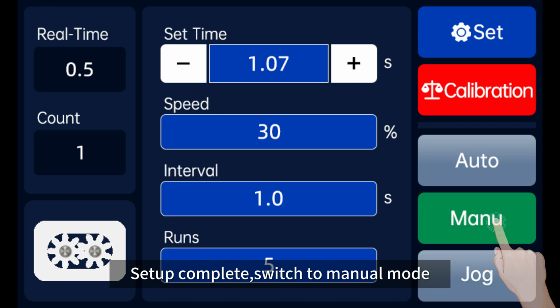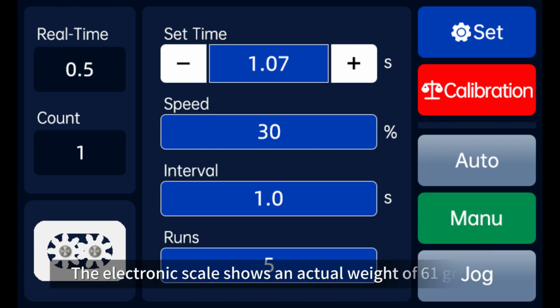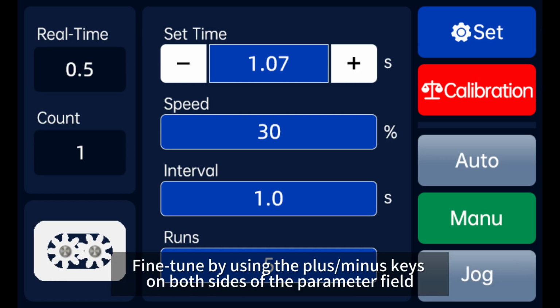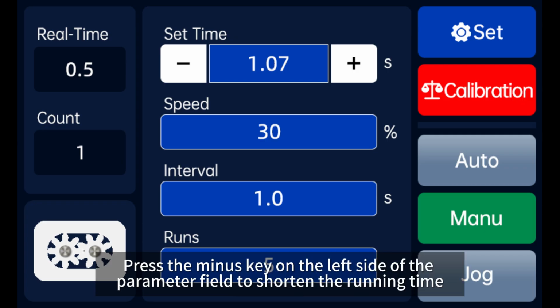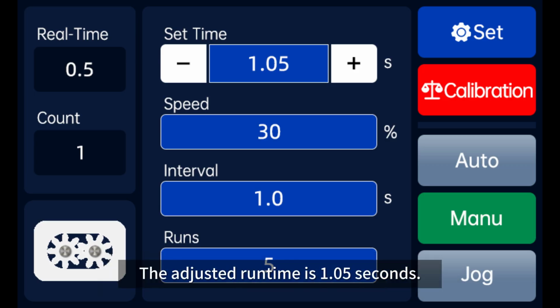Setup complete. Switch to manual mode. The electronic scale shows an actual weight of 61 grams. Fine-tune by using the plus/minus keys on both sides of the parameter field. Press the minus key on the left side of the parameter field to shorten the running time. The adjusted runtime is 1.05 seconds.